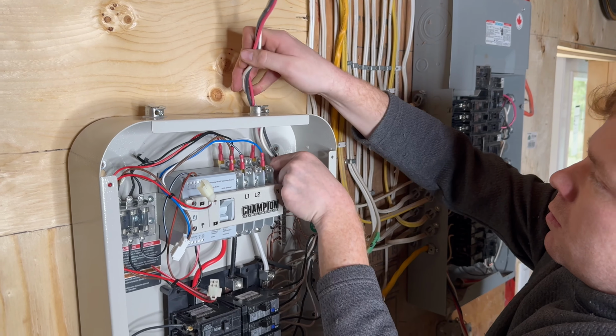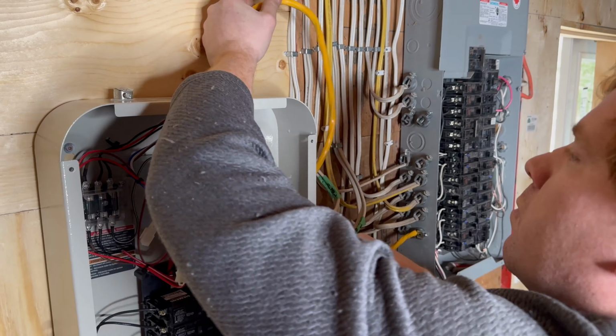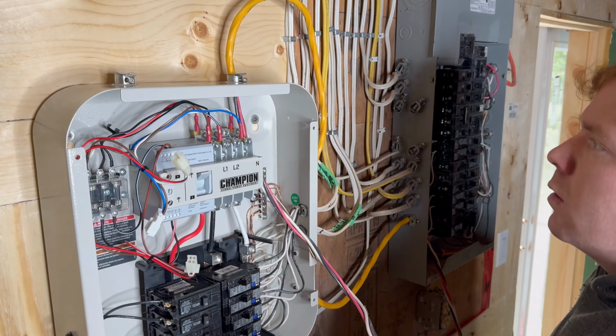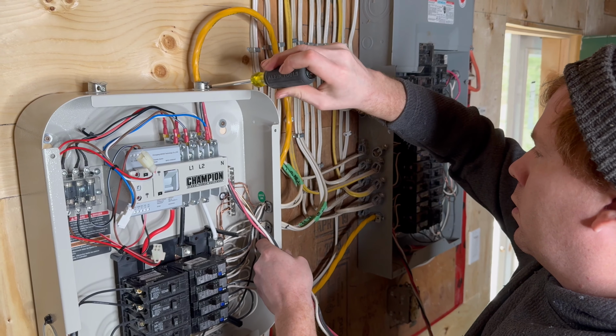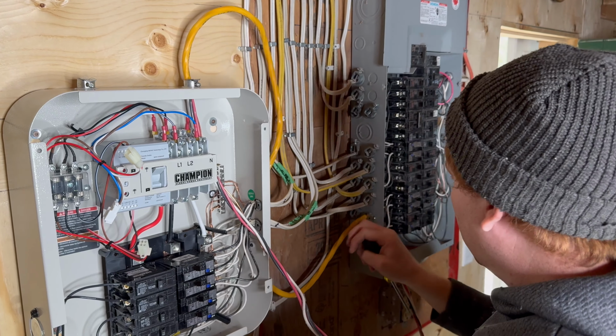Regardless of the size of transfer switch you're installing, you'll need to use double pole breakers. So these provide 2 phases of 120 volts for a total of 240 volts when you need it for something like a stove or a dryer.